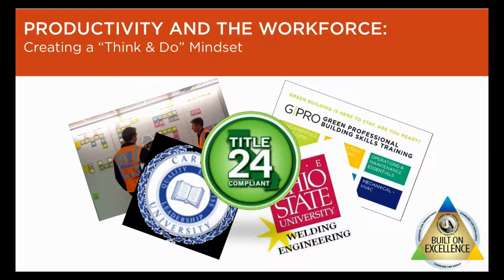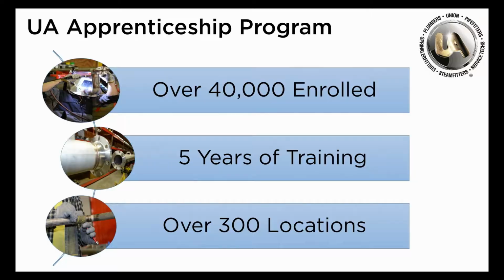Does that make sense? Have you heard of that before? You prove it on the day you leave—not just that it's running, not just that the pumps are flowing water, not just that the compressors are pushing refrigerant, but that the combined energy of the compressors, pumps, and fans meets the goals it was designed for. Title 24 went a long way. In a couple of years, we were approved as a provider, so our members can now sign the documents, take the measurements, and do the work knowing that when they hand the building off, the building owner gets the energy performance he was promised.